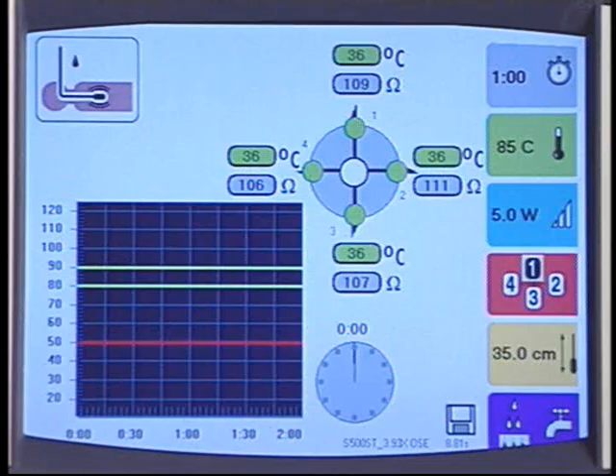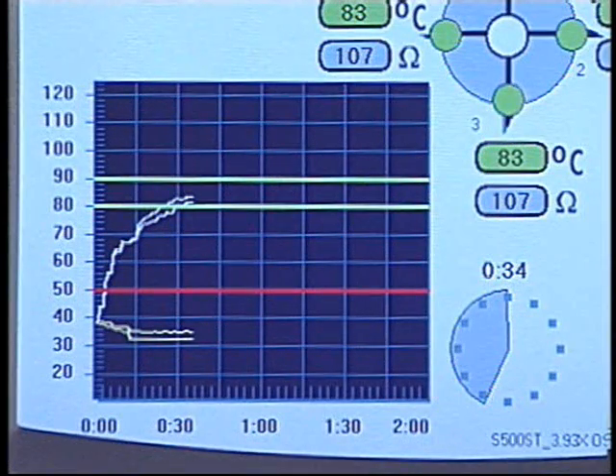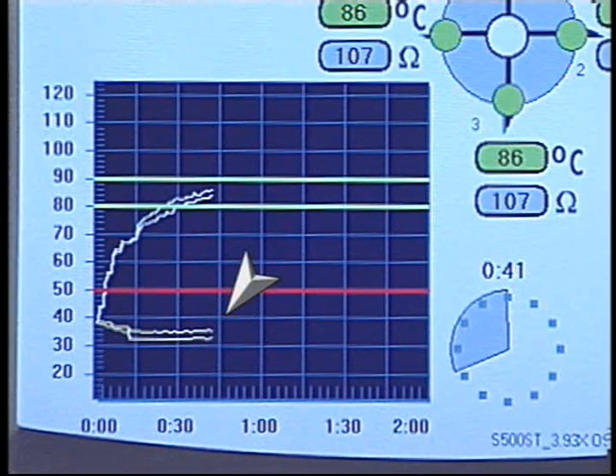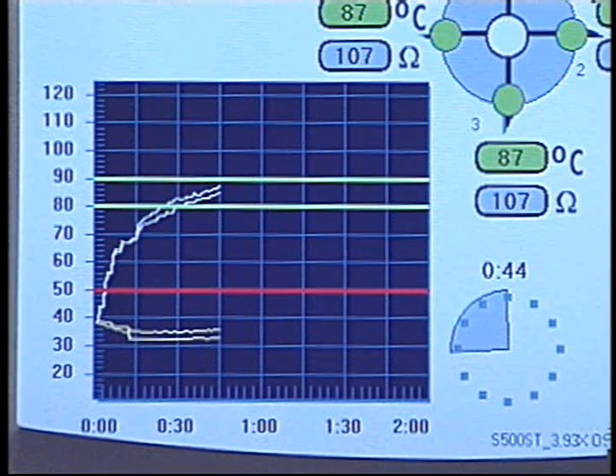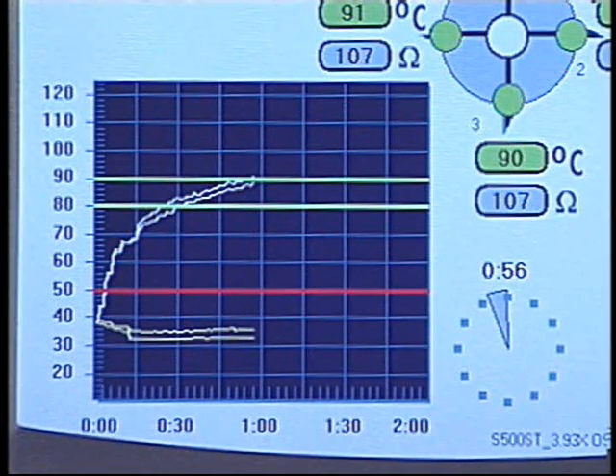The treatment screen will be displayed with real-time temperature curves on the left of the screen. The upper curves represent the highest and lowest of the 4 tip temperatures, while the lower curves represent the highest and lowest mucosal temperatures. The tip temperatures increase with time towards the target temperature of 85 degrees Celsius, while the mucosal temperatures are maintained at a low temperature by the provision of constant irrigation to the mucosal surface. RF delivery will cease automatically when the treatment time of 60 seconds is reached, at which time the screen will dim to a gray color. A beep sounds when the treatment is completed.